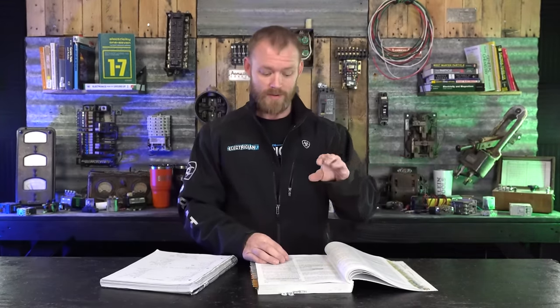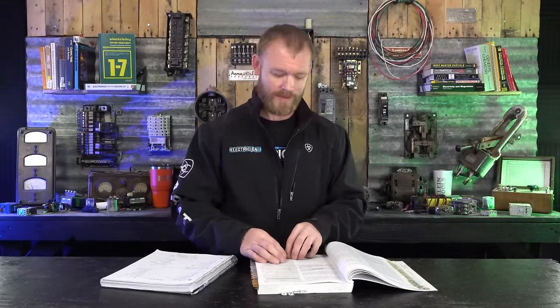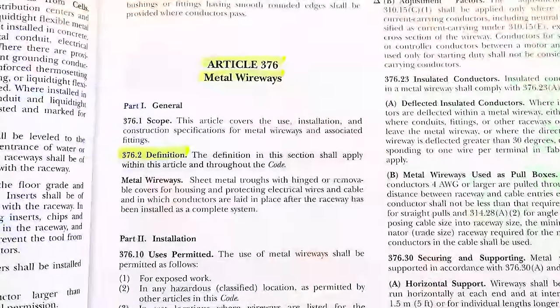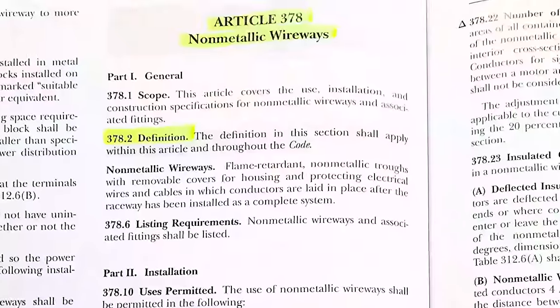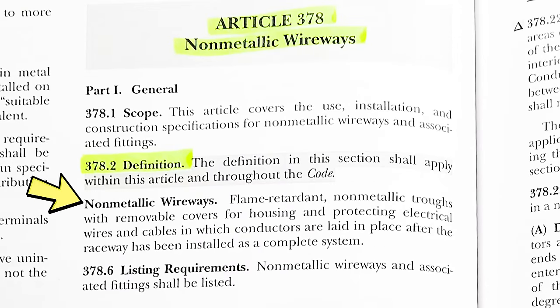You're not going to find the definition in the beginning where all of the other definitions are of things that apply pretty much throughout all of code. You're going to find the definition within the article. And that's going to happen a lot of places in code with a lot of these words. So the definition of a metal wire way is a sheet metal trough with hinged or removable covers for housing and protecting electrical wires and cable and in which conductors are laid in place after the raceway has been installed as a complete system. So plastic, pretty much the same thing. Non-metallic is a flame retardant non-metallic trough with removable covers and housing to protect electrical wires and cables in which conductors are laid in place after the raceway has been installed as a complete system. So same thing, just one of them is metal, one of them is not.